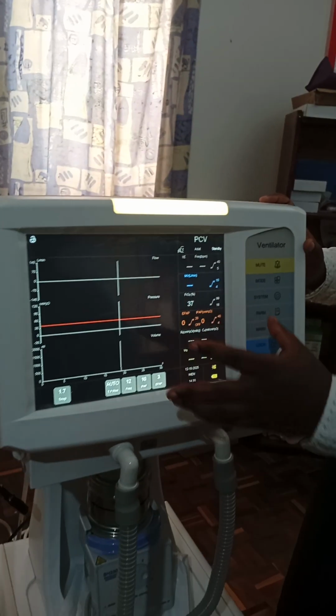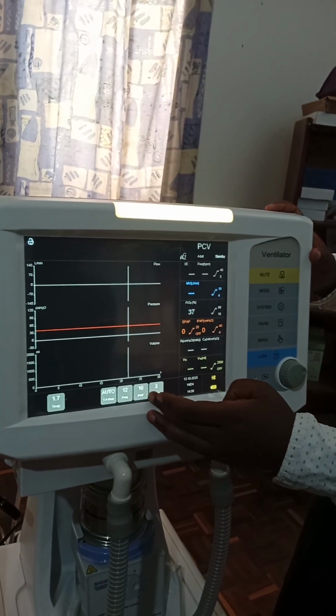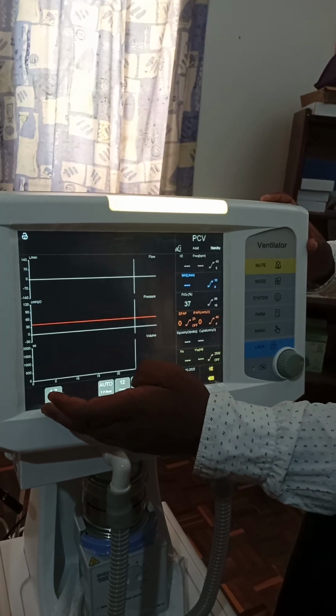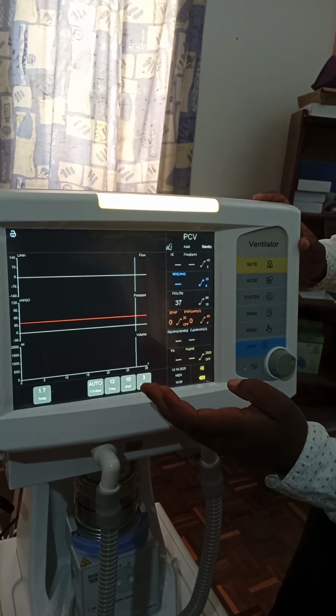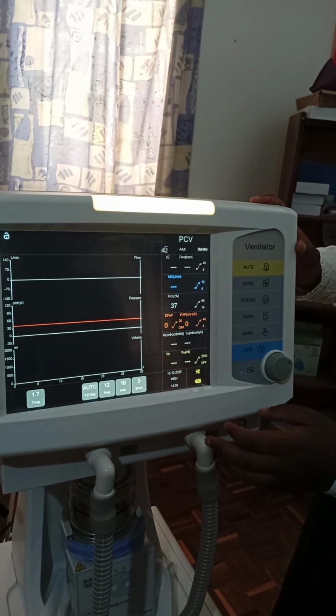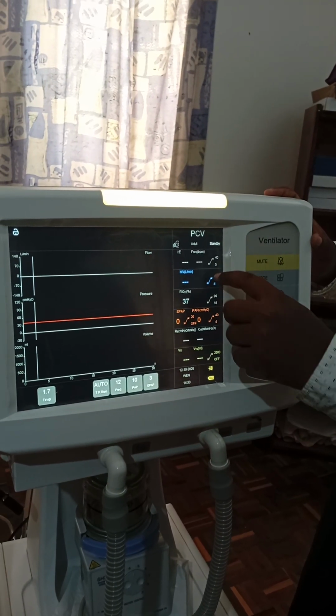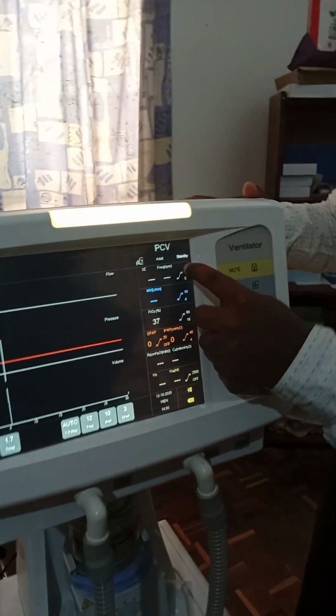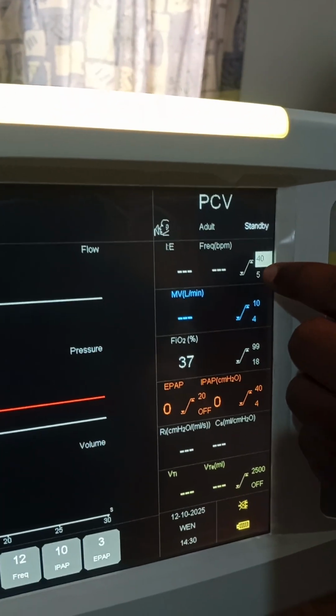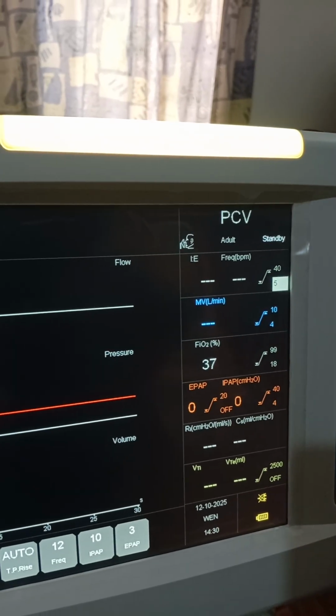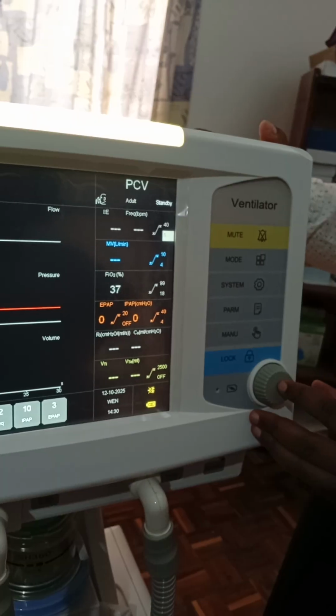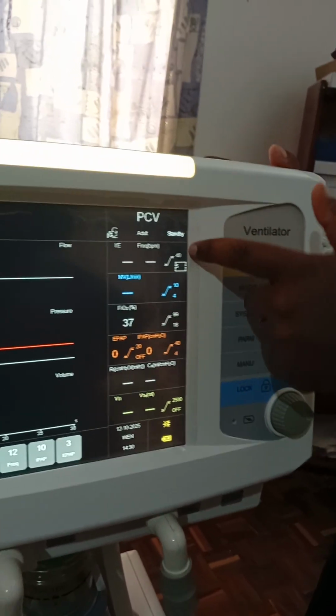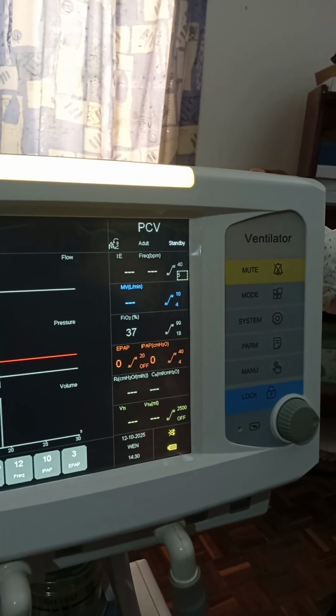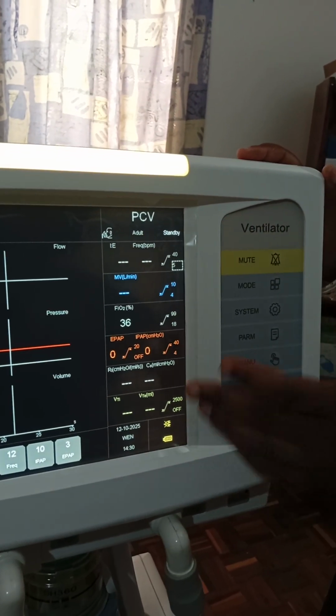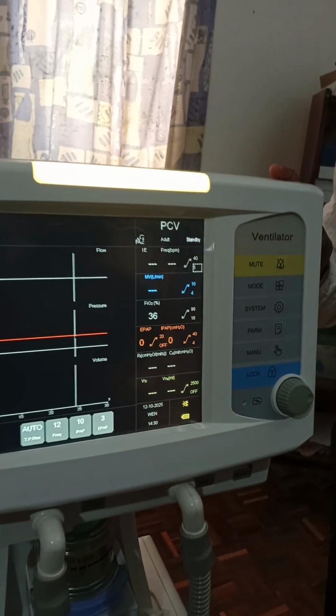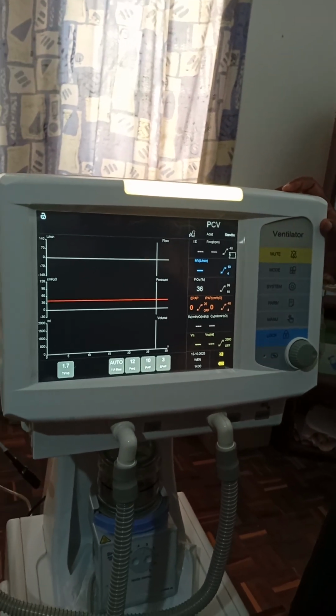Here you see we have the different displays. These are the parameters, like the frequencies and the ratio of inspiration. We also have expiration parameters. Here we have the alarm levels indicated on the screen. You can directly change the alarm levels by selecting on the screen, and then adjust with this knob. Once you adjust to the required level, you confirm. But for these ones, you don't need to change them because they are already standard based on the factory calibrations.